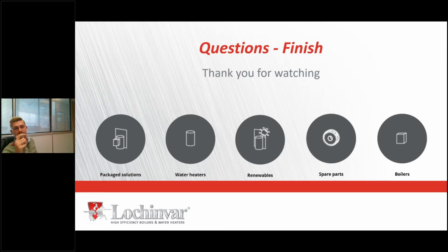Last question, I think. Can your heat pumps be cascaded and what is the maximum output? Okay, I'll keep it as brief as I can because there are 3 different heat pump ranges we do. The low temperature range is 20 to 464 kilowatts, and they can be cascaded up to 6 heat pumps. So we're potentially looking at 2.7 megawatts of output from the low temperature. The high temperature range is 8 to 100 kilowatts, and those can be cascaded up to 6 units as well. And our boost range is 30 to 496 kilowatts, again cascadable up to 6 units.